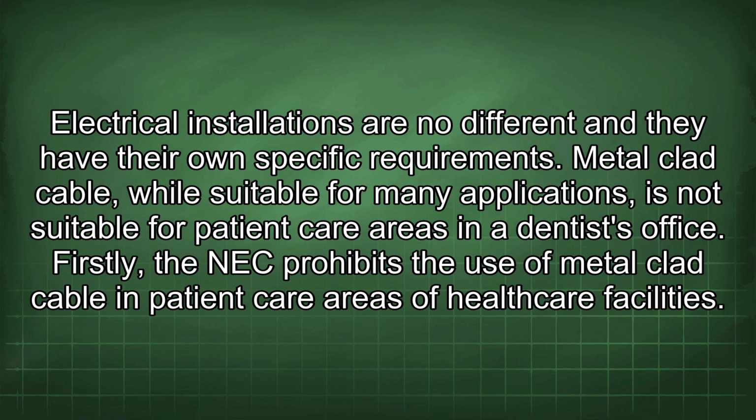Metal-clad cable, while suitable for many applications, is not suitable for patient care areas in a dentist's office. Firstly, the NEC prohibits the use of metal-clad cable in patient care areas of healthcare facilities.